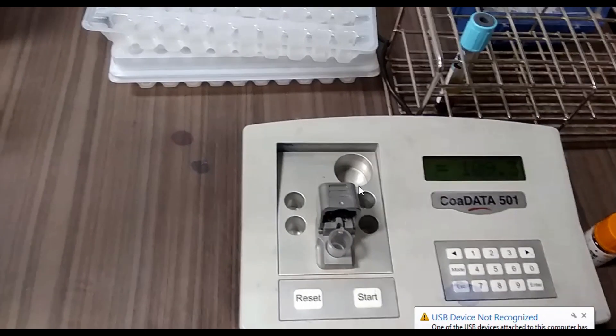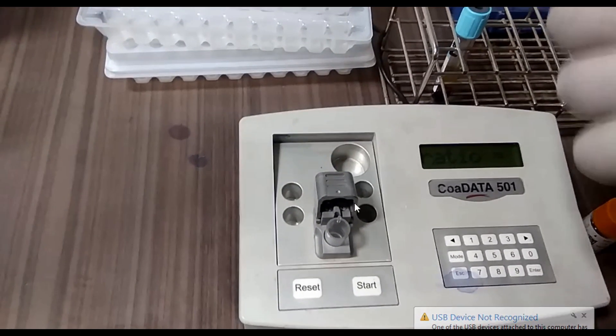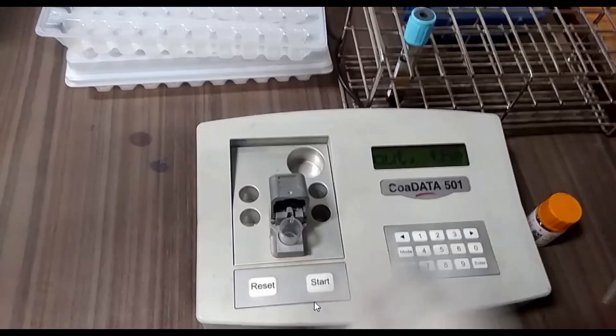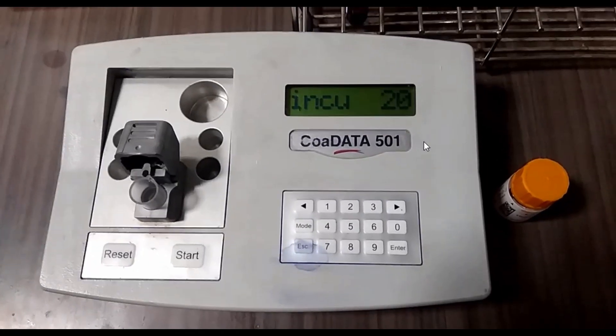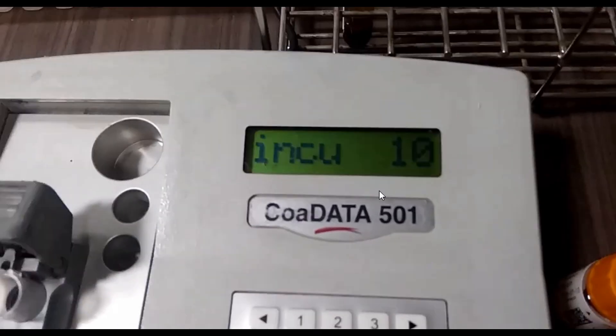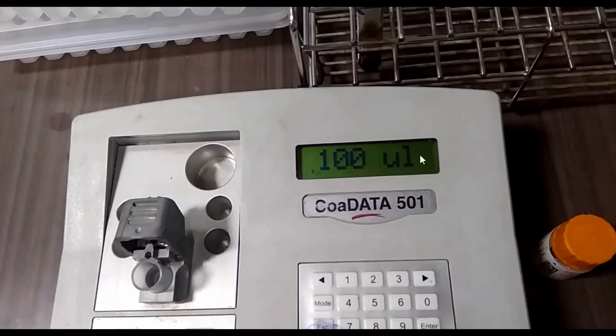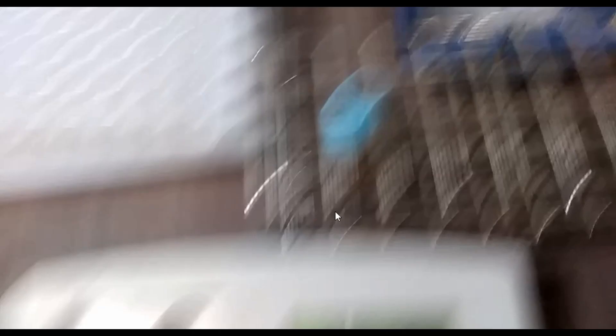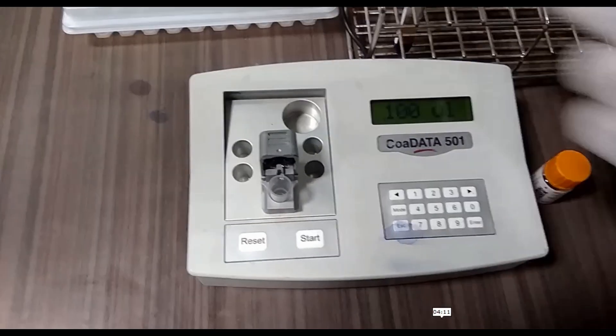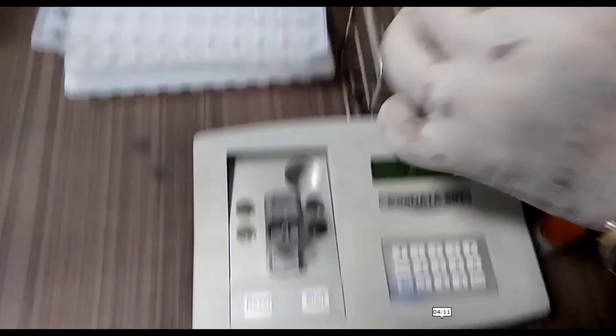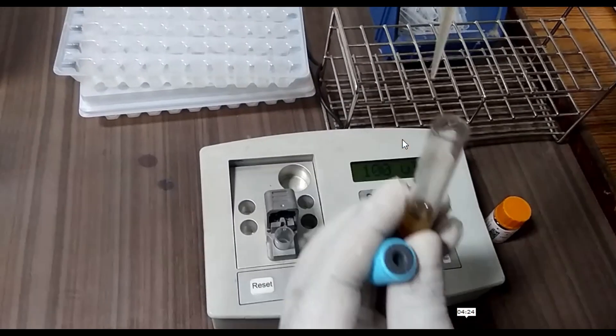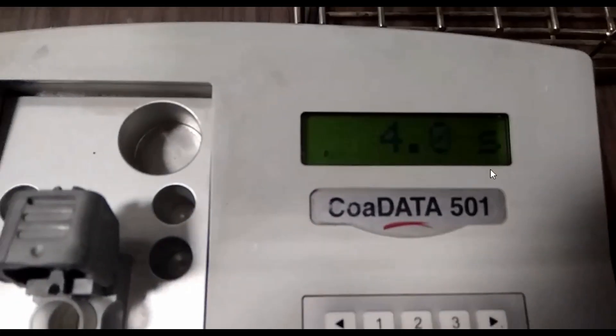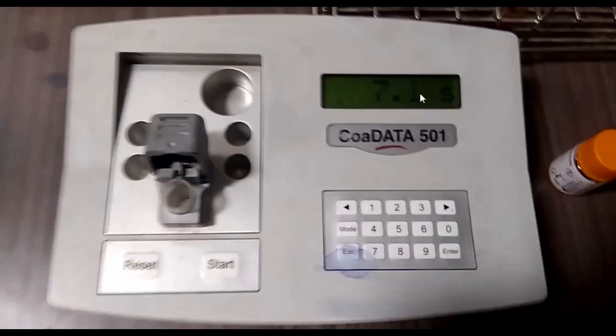This is the incubator. Now push the start button. Incubation time will be displayed here, that is 30 seconds. After completion of incubation, add 100 microliters citrated plasma. Just after addition of citrated plasma, the coagulometer will start to capture prothrombin time.